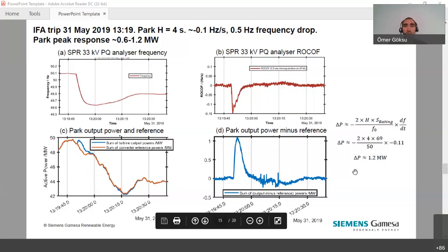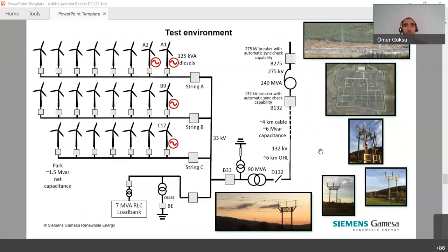And this is like a 1 minute range. And then in summer 2020, again a 2 months testing was done with advanced grid forming technology or more functions. You will see here where various tests were done. For instance, these four turbines were operated as grid forming, and then there was energization of other turbines and resynchronization, and energization of this 240 MVA transformer with direct online energization with some inrush, and closing and opening these breakers here, and also islanded operation again with a load in the wind farm.